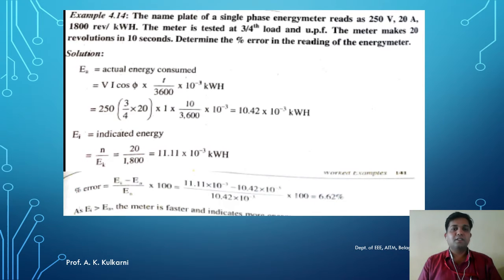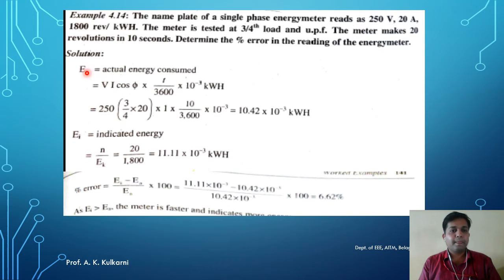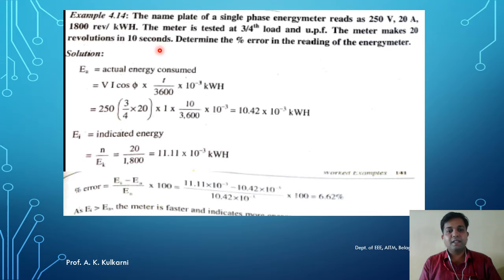Now let us solve some problems on these errors in energy meters as well as the wattmeter. Let us consider our first problem. The name plate of a single-phase energy meter reads 250 volts, 20 ampere. It has 1800 revolutions per kilowatt hour. The meter is tested at three-fourth load and unity power factor. The meter makes 20 revolutions in 10 seconds.